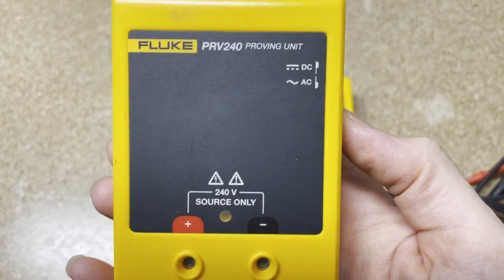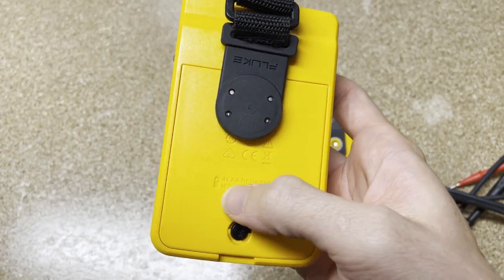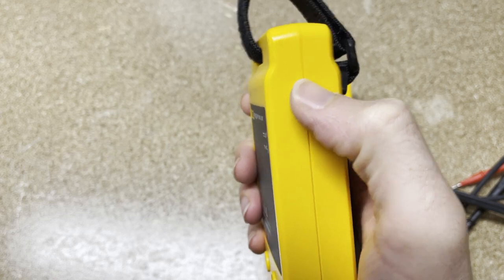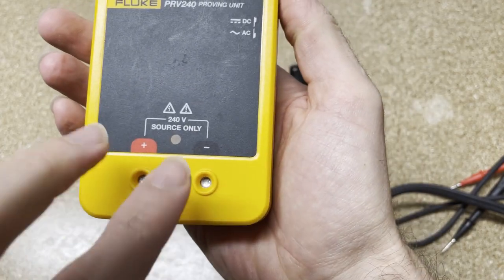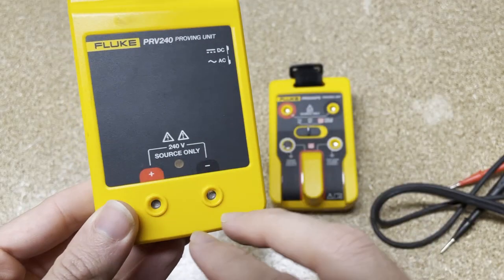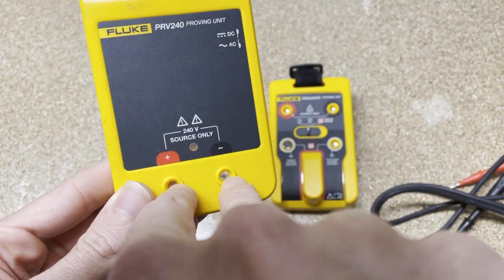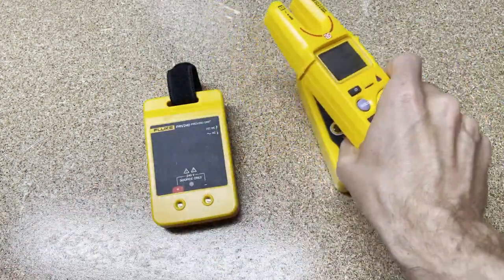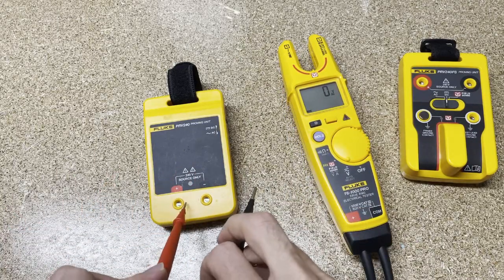We have two different units. The first one that came out is the PRV240. What you see here is it comes with a magnet pack powered by four AA batteries. You've got a toggle that goes up or down — up is DC, down is AC — and that's going to be the voltage it outputs. There's no on/off button. The way you turn it on is by initiating the contacts by pushing the test leads down into it. I'll demonstrate with my T6, and this method can be used with any multimeter.